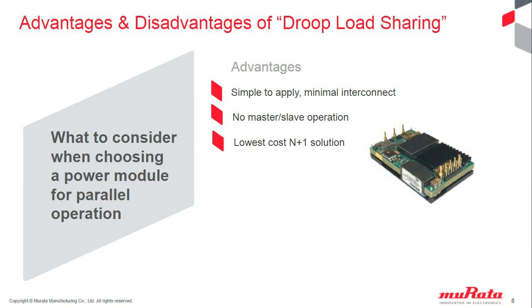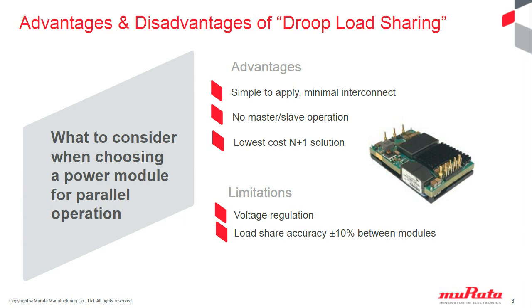So what are some of the limitations? We talked about the voltage regulation being approximately plus or minus 5% of the output voltage, nominal. In an intermediate bus application where your load is point-of-load converters, those point-of-load converters normally have an input voltage range of 7 volts to 14 volts. So the slight droop in the output of these modules has no effect on those converters. With the load share accuracy specified at plus or minus 10% between modules, you may have an application where you need very tight regulation of the output. This may not be a solution for that particular application. But for an intermediate bus converter driving point-of-loads, this is the lowest cost solution available.